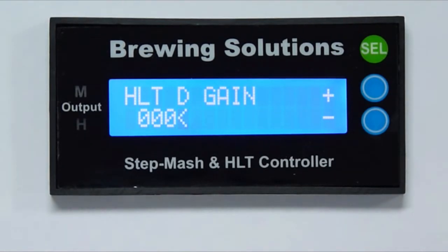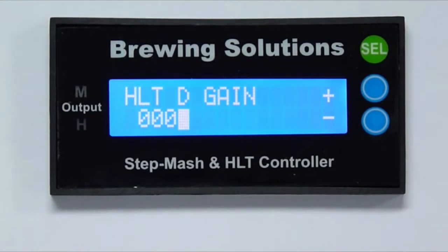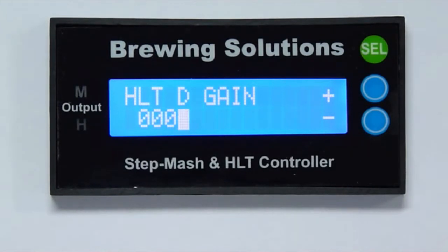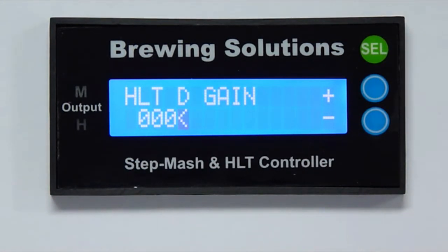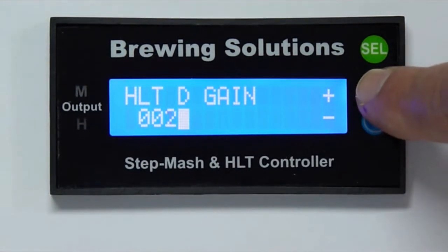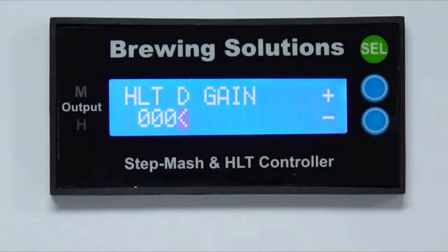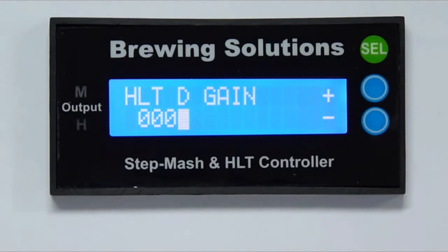For the derivative, 0 is the factory default setting for the controller. A value of 0 derivative is a special function for this controller that will configure it as a PI-only controller. PI control is recommended for direct heated systems. For heat exchange systems, some derivative gain is recommended but used conservatively. Any derivative value above 0 will configure the controller to PID. Use the blue buttons to increase or decrease the derivative to the desired setting. I will select 0 for the derivative; control settings will be saved, ending the controller setup and returning us to the main menu.